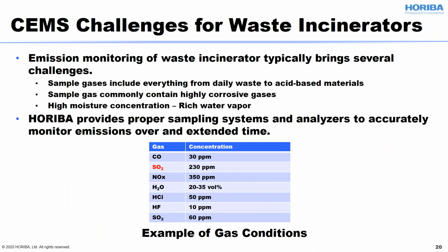I'm going to explain the issues for all of the CEMS players. Let me explain what the gas looks like. Emission monitoring of a waste incinerator typically brings several challenges. The sample gases include everything from daily waste to acid-based materials. The sample gas commonly contains highly corrosive gases and also high moisture concentration, rich water vapor. HORIBA's answer is to provide the proper sampling system and analyzers to accurately monitor emissions over an extended lifetime. This is one of the tables showing an example of the gas condition from an incinerator. You can see there is much SO2, or sometimes HCl or HF, harmful components inside.